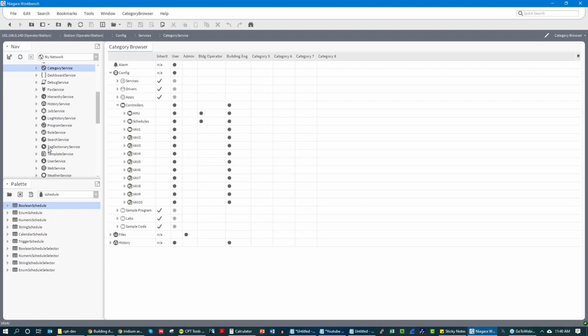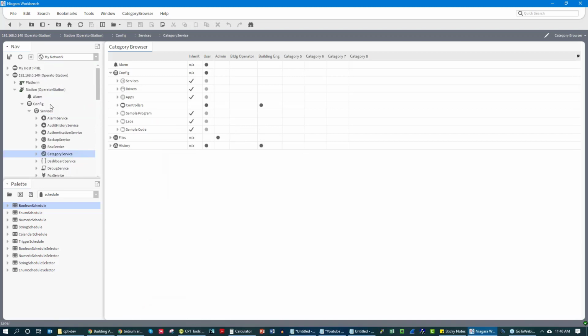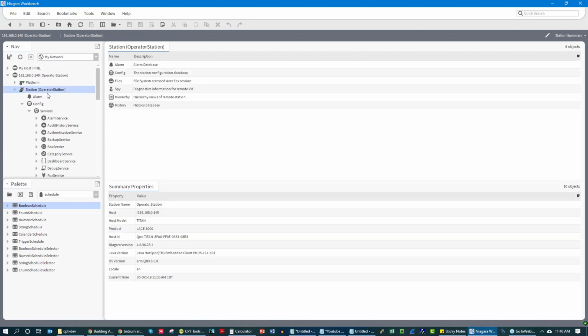categories and roles. Now, this will look different based on whatever manufacturer's software you're using, but these terms are pretty synonymous across the board. You have user types or roles, and those roles are associated with categories that allow you to get very granular. You can see, right, I can pick what points they can actually see, control, and interface with. Once all this is set up, then you have a functioning building automation system.